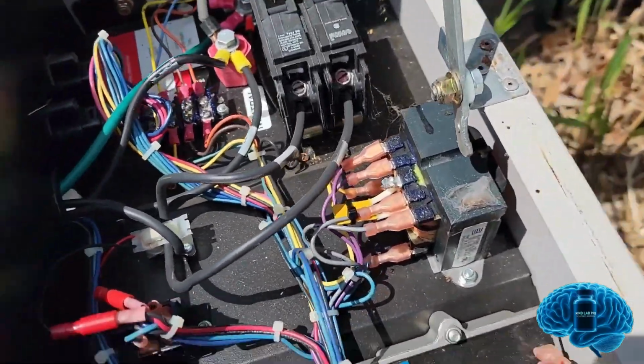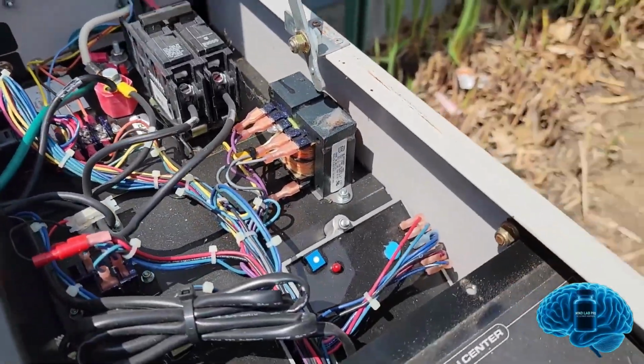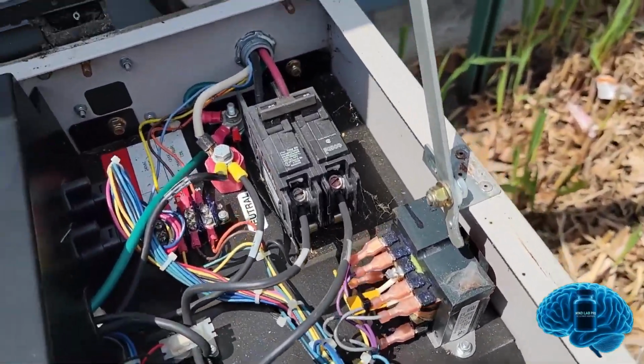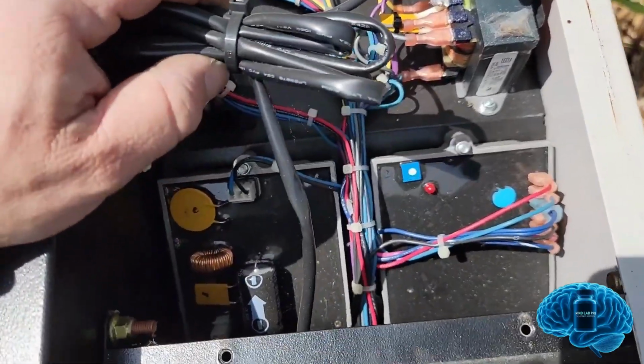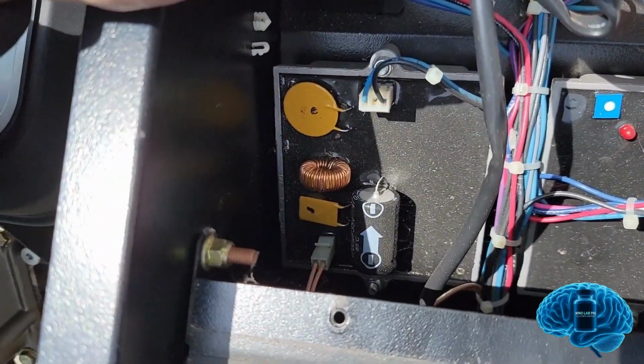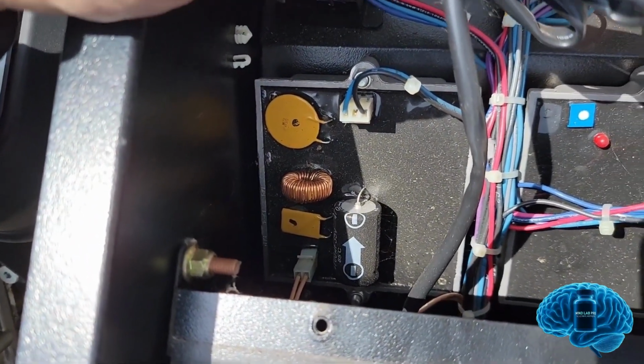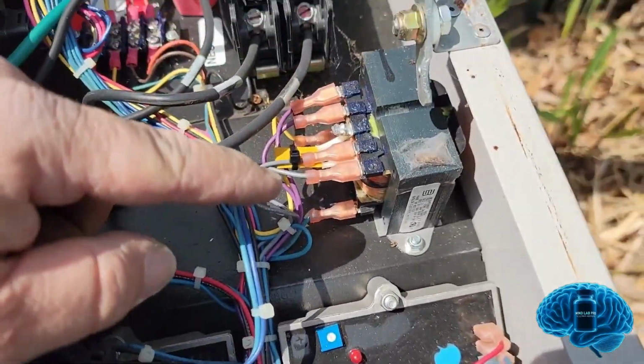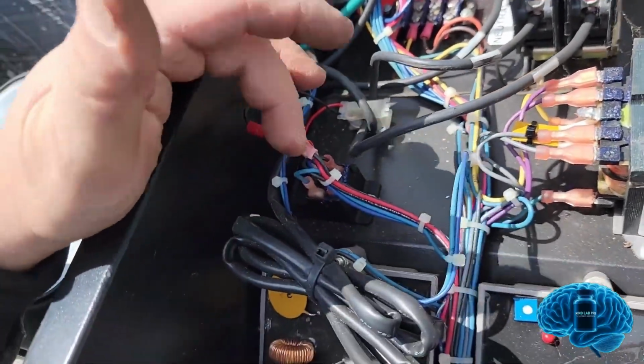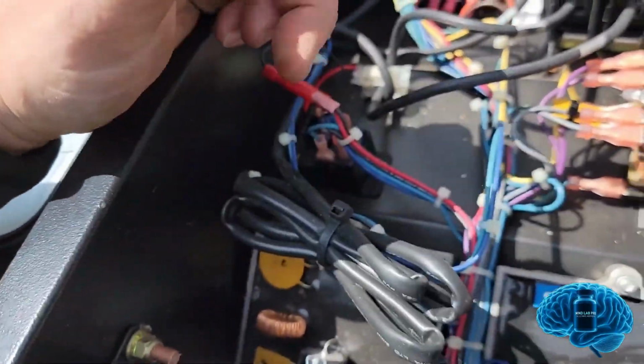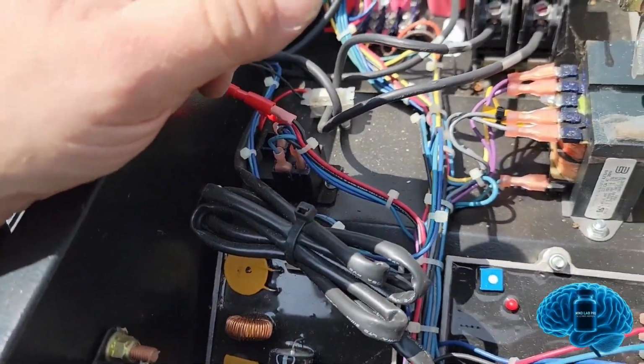You've got your dual tap transformer here. This is for the battery charge circuit. It takes the 230 volts from the house and turns it into about 18 volts for the battery charger there. And when the generator's running, it uses the other windings for the battery charger. And then they use a relay to switch in between that, which they got rid of all that since they found out it was kind of dumb.